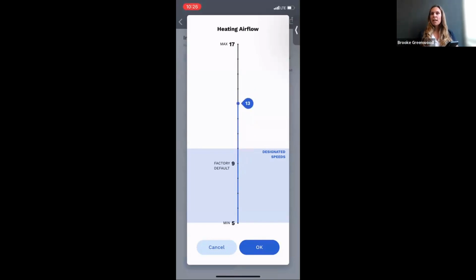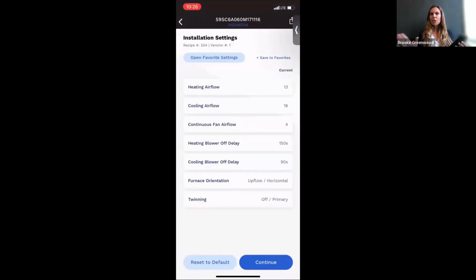When I look at my airflow tables to see what airflow I need, I leave it where I want to set it and select OK. So we've just adjusted the heating airflow. Again, nothing's been done to the control at this point in time because I haven't done my tap to communicate back and send the updated changes.